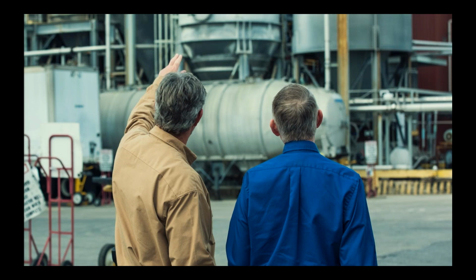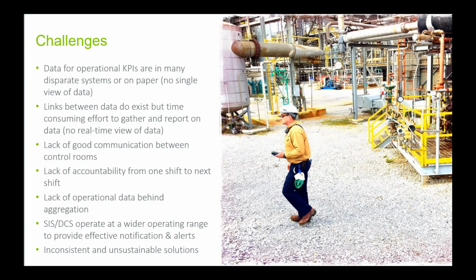They're supposed to look at the access port on the motor to make sure the motor heater circuit is pulled in. What that means is that those large vertical motors had a little 110-volt circuit inside the motor that would be on if the motor was off, to keep the motor warm and dry. So when you hit the start button, it wouldn't go to ground and all of a sudden short out. It wasn't written down anywhere, but it was one of those things they were, quote, supposed to do.